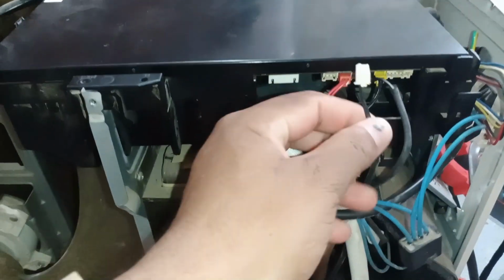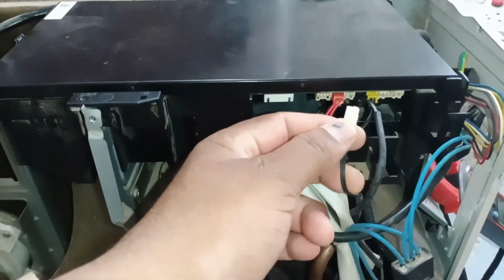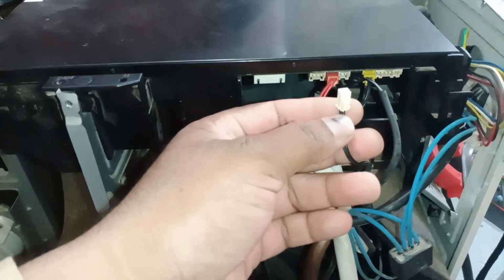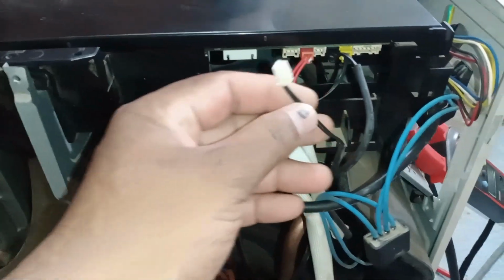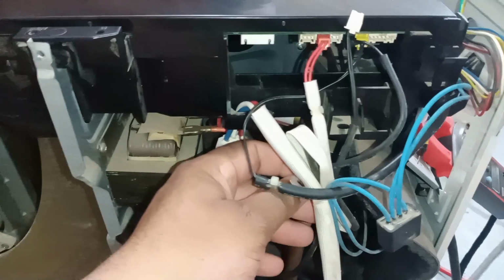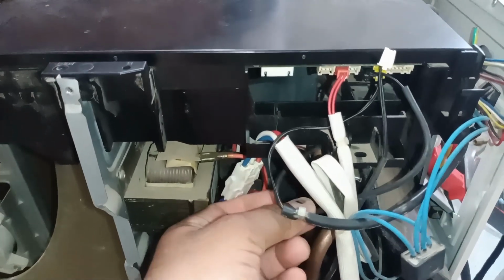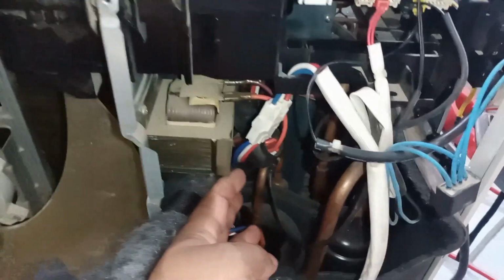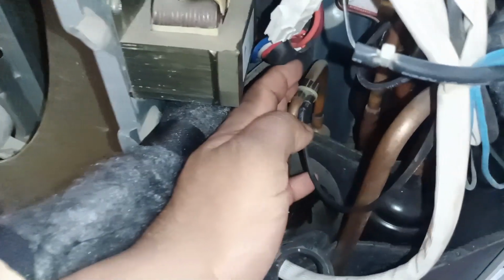Apart from this, the sensor itself may become short-circuited, so you should check that as well. You must also know the resistance value of this sensor. If you replace it with a sensor of the same resistance value, your unit will return to working condition. Now, let me show you where the discharge pipe sensor is installed in the outdoor unit. The sensor is attached here with a clip.